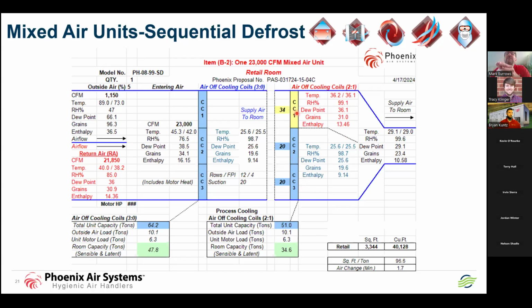Even if we're in defrost, look at the discharge dew point. The discharge dew point is 29.1 degrees. Is that a safe condition? Well, the dew point of the return air is what? 36 degrees. So we can take these anywhere probably on the low side to 35 degrees. We probably can't get much colder than that, but we're seeing more and more facilities, their QA folks, like the fact that, though the employees certainly don't like it, as far as retarding bacteria, they like to run these colder and colder. If you're going to do that, you're going to need something like this.